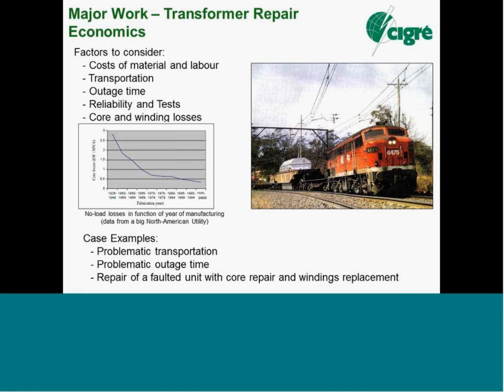That graph there just gives you a useful picture of how core loss, in watts per kilogram, has declined in core steel with improvements of core steel. So it may be that for a very old transformer, the improved core loss may tip the balance in favour of a new transformer, just on the loss reduction.